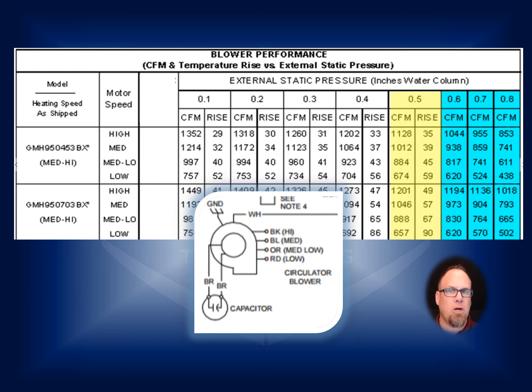Now you go to medium-low, chances are between medium and medium-low, you probably won't drop to another static level, so it'll probably stay right in that same guideline there. So you probably drop down to maybe around 741 in this instance, and then once you drop down to the low speed, you're going to be at that 620 CFM range. Hey, and those are examples. Those are not standard by any means. You know, there is no such thing as standard. Every install is different. Every piece of ductwork in every home is a little bit different.